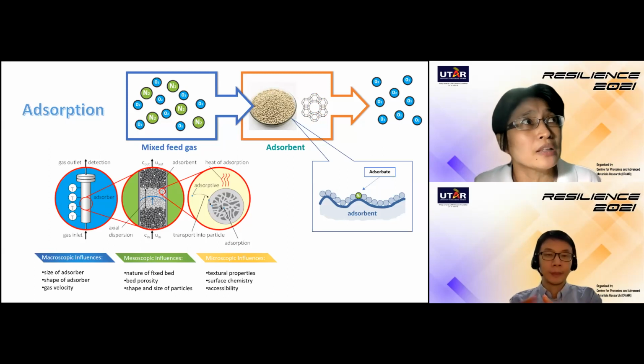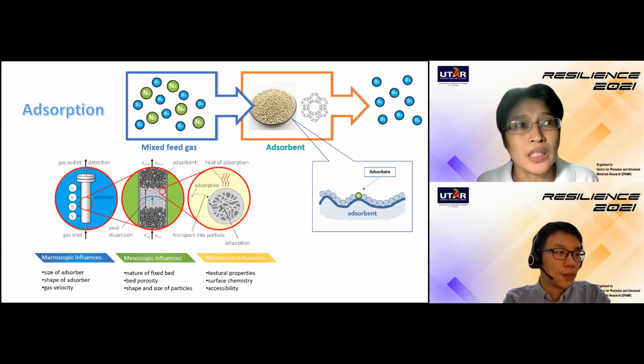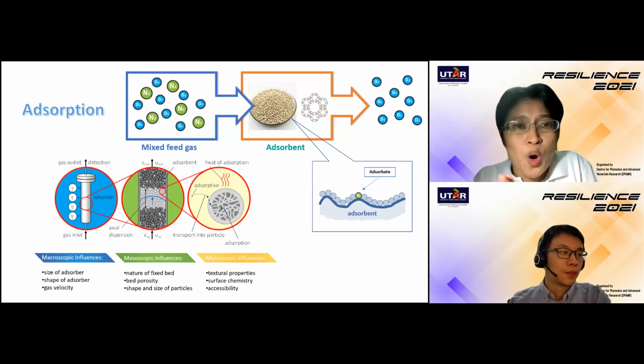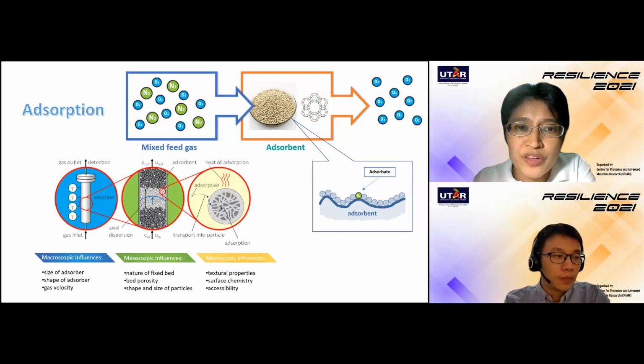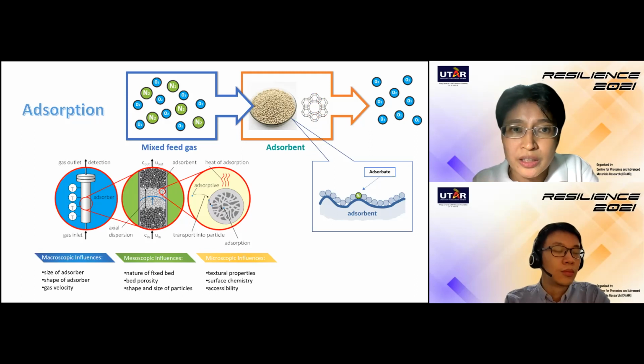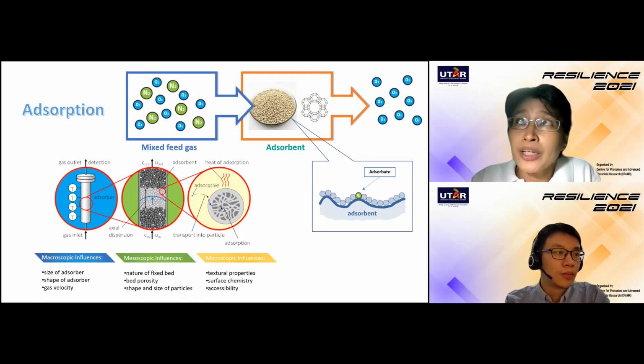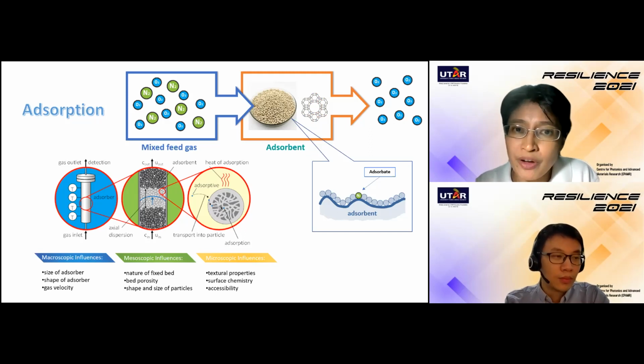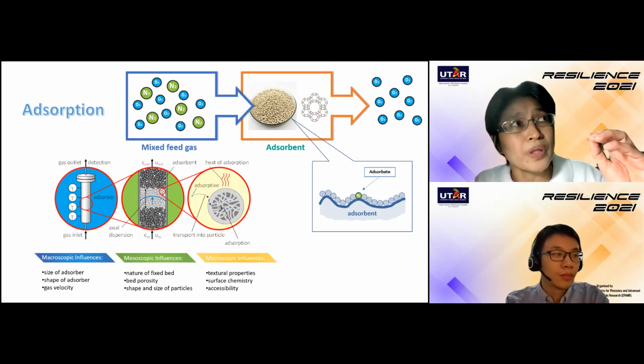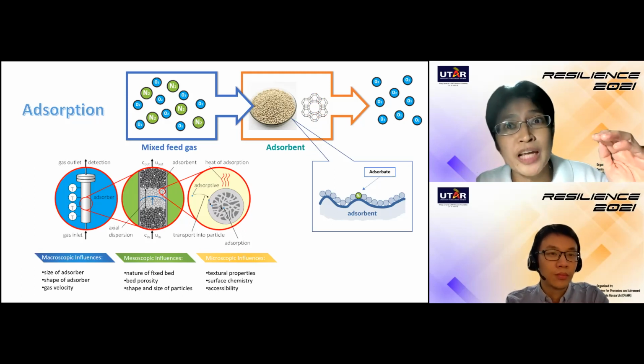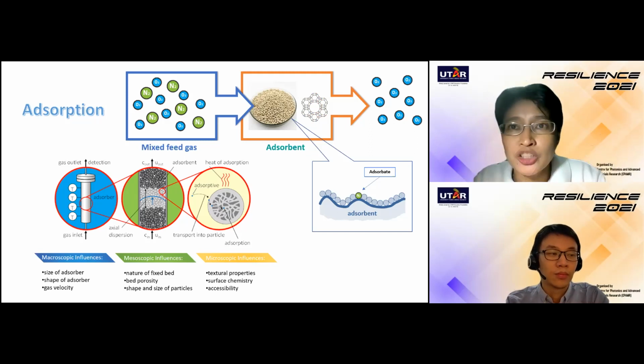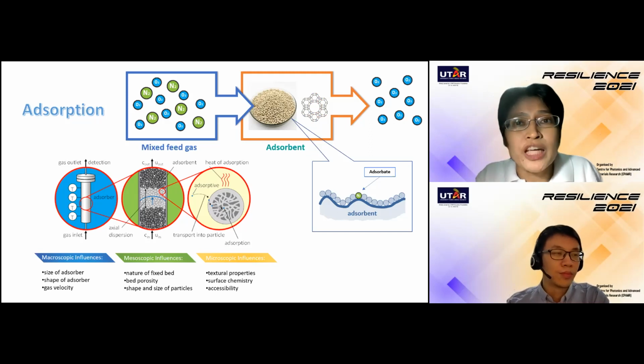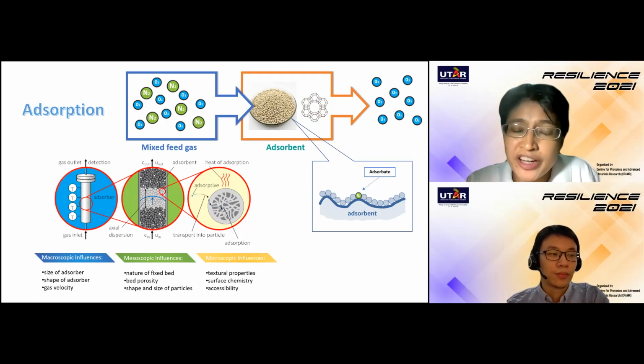That's why the process is termed pressure swing adsorption, because when one column's zeolite is filled up with nitrogen, it has to be regenerated. This is done by decreasing the pressure to ambient atmospheric pressure. We also need to split a certain quantity of the oxygen product from another column to purge the zeolite, so the oxygen purge gives better regeneration in addition to reducing the pressure.